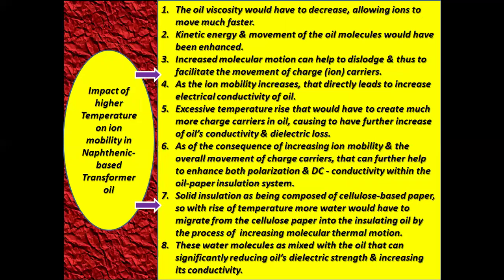Impact of higher temperature on ion mobility in naphthenic based transformer oil. The oil viscosity decreases, allowing ions to move much faster. The kinetic energy and movement of the oil molecules are enhanced. Increased molecular motion can help to dislodge and thus facilitate the movement of charge ions, that is, charge carriers.